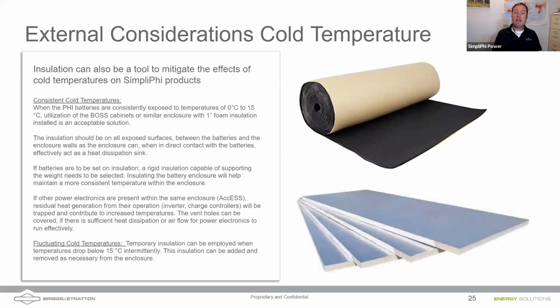One way we can do that is insulating underneath the batteries so we're not getting conduction going through that cold metal shelf into the battery. We can also address convection by shutting down the ventilation fan, or potentially turning a fan on in hot weather. And by minimizing radiation, since you've got a big metal cabinet sitting out there in the clear night sky, we can think about covering it and providing some sort of overhang to prevent radiation loss.